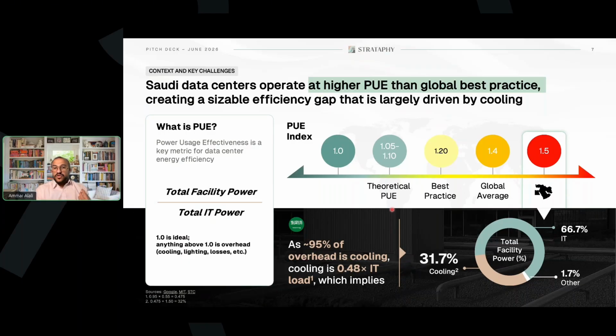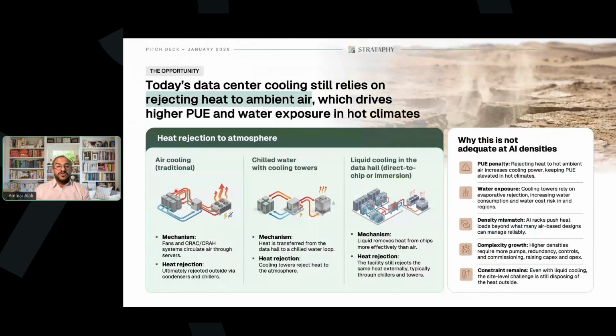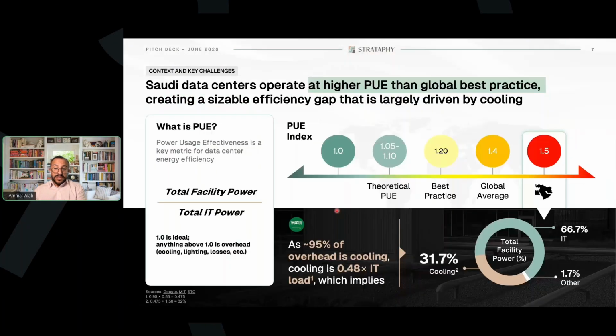The theoretical limit is closer to 1.05, 1.1 for mechanical PUE, because you always have losses in the cables and the connections. Best practice is getting that number to 1.2. The global average used to be 1.4, and now we're seeing it lower, closer to 1.3 or 1.25.